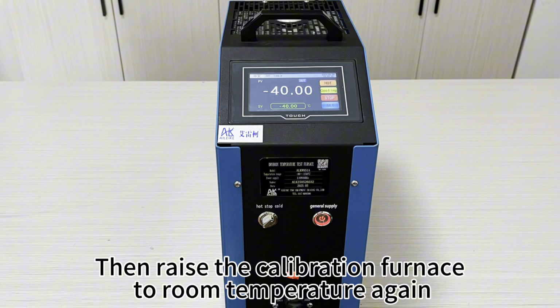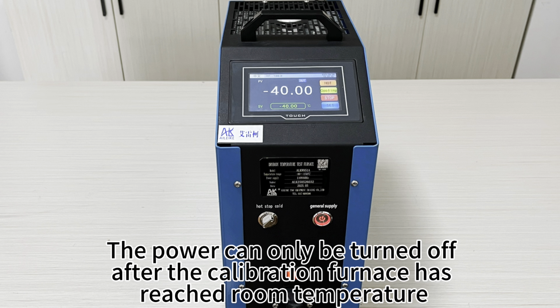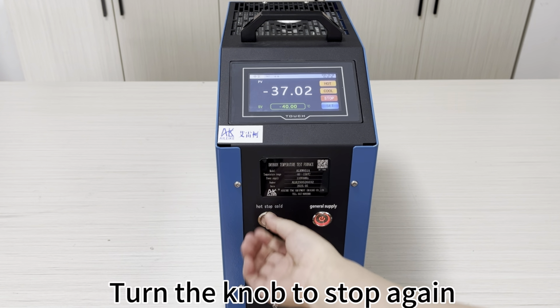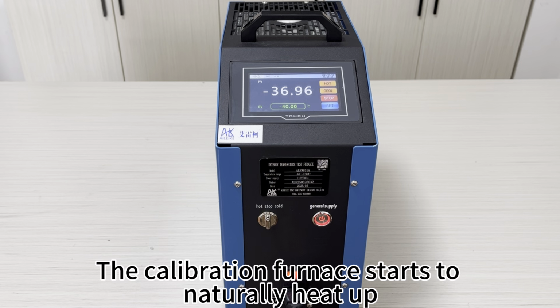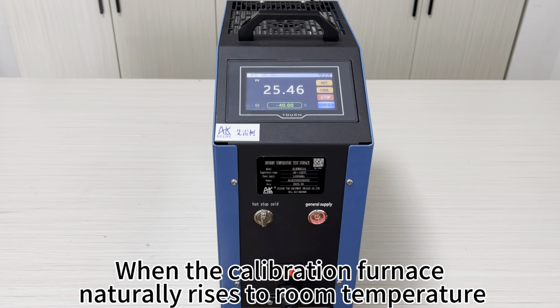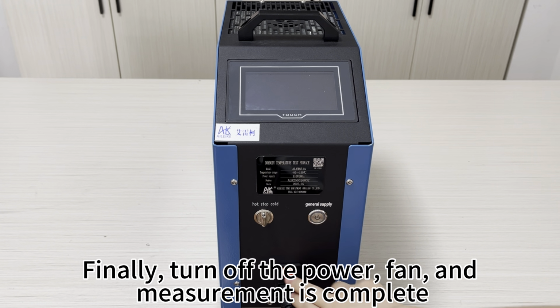Then raise the calibration furnace to room temperature again. The power can only be turned off after the calibration furnace has reached room temperature. Click the stop button first. Turn the knob to stop again. The calibration furnace starts to naturally heat up. When the calibration furnace naturally rises to room temperature, finally, turn off the power fan and the measurement is complete.